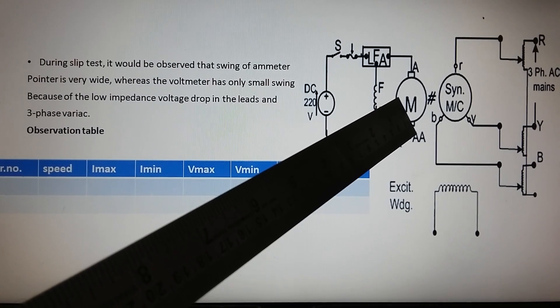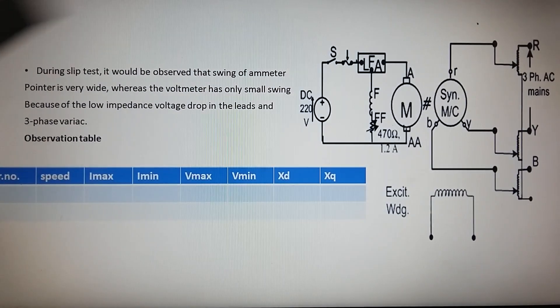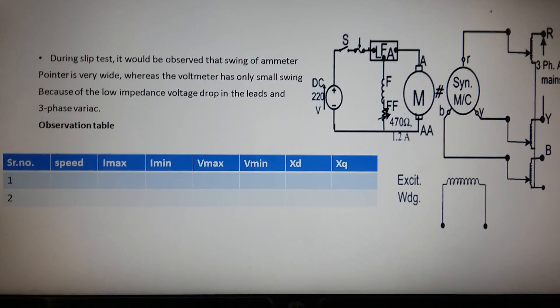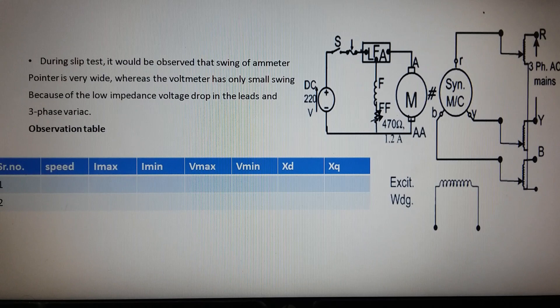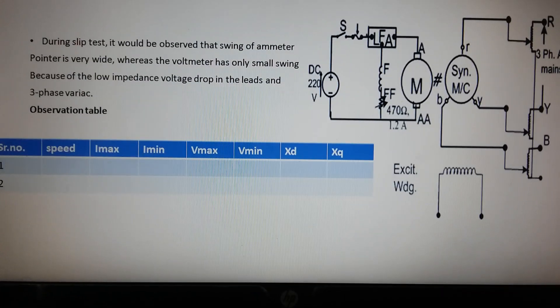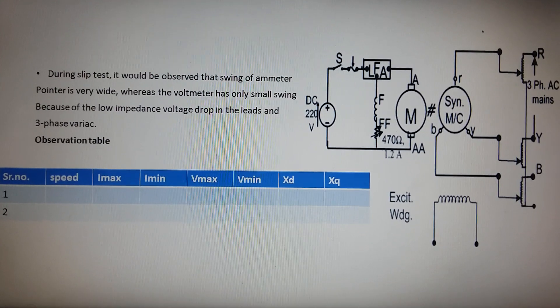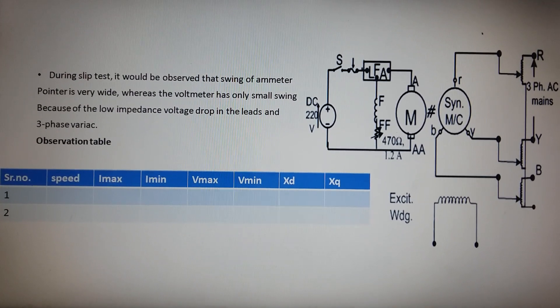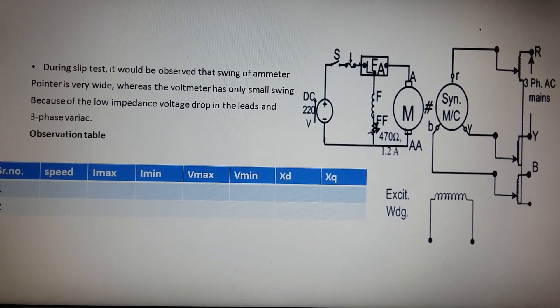So the two requirements for successful determination of Xd and Xq are: first, the slip should be kept small; and second, the supplied voltage should be kept low. That is all.